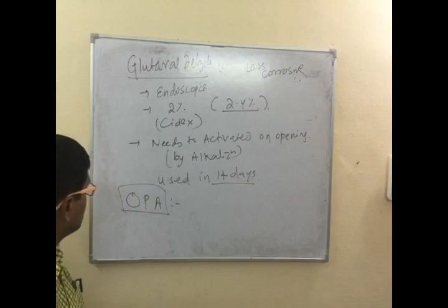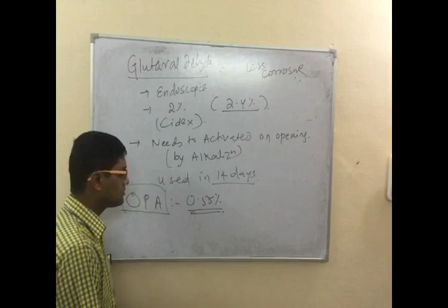It is a better acceptable disinfectant than glutaraldehyde, and 0.55% concentration is mostly used. Okay, and the advantage of orthophthaldehyde is that activation is not required. The alkalization leading to activation, which is there for glutaraldehyde, that step is not there for orthophthaldehyde.